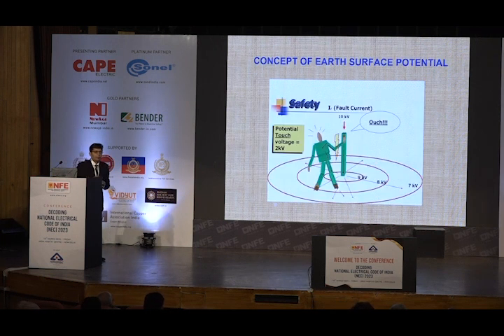What happens when there is a fault and the fault starts flowing through your electrode? Around that electrode there will be one thing that is called the earth surface potential, and because of that ESP there is another term, touch potential and step potential. This earth surface potential is responsible for the most popular words, touch potential and step potential. These are basic pictorial interpretations to understand that concept.